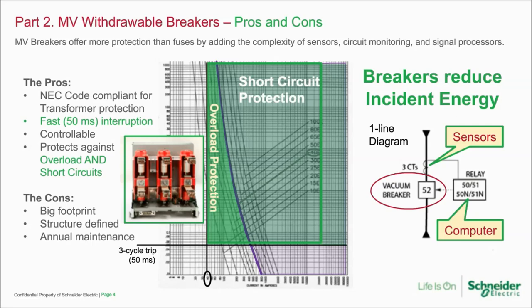The cons here are that the consequence of metal clad switchgear using withdrawal breakers is that they're fairly large, and the structure is very well defined in the standards — meaning all manufacturers have fairly similar solutions with only a few differentiators. We still have the issue of annual maintenance. Because of the shape and size of the interrupter connections — finger clusters — we have to watch out for issues in that region.